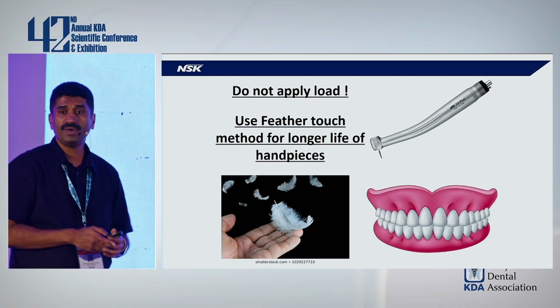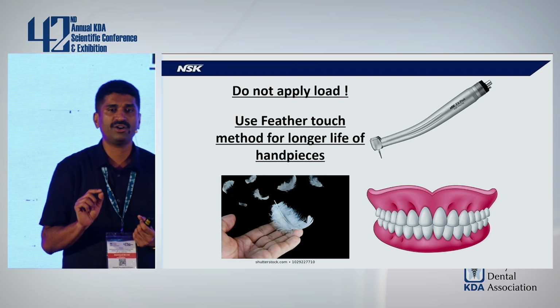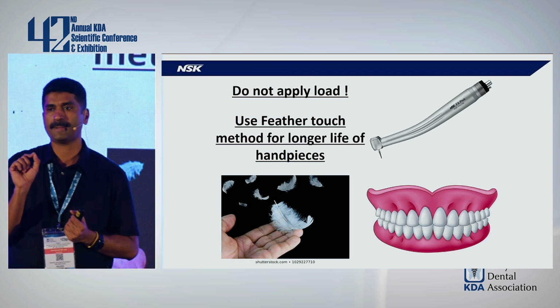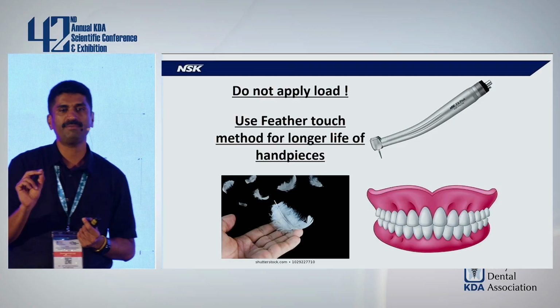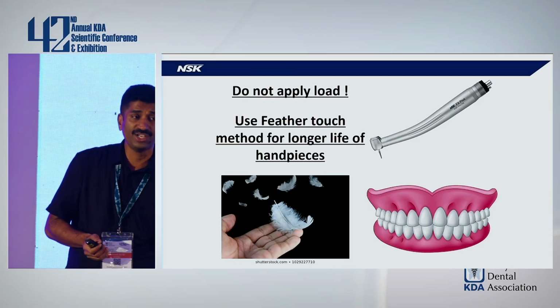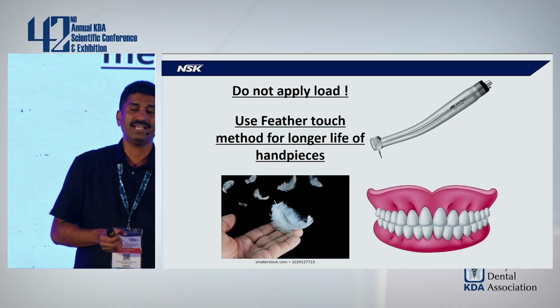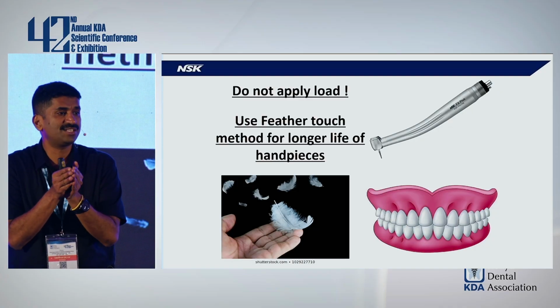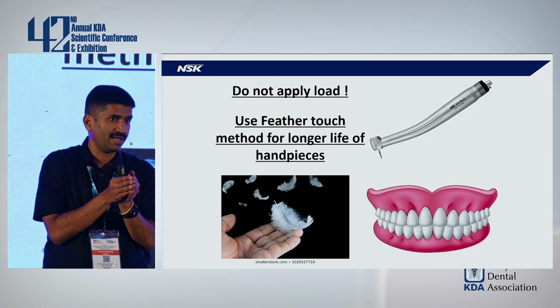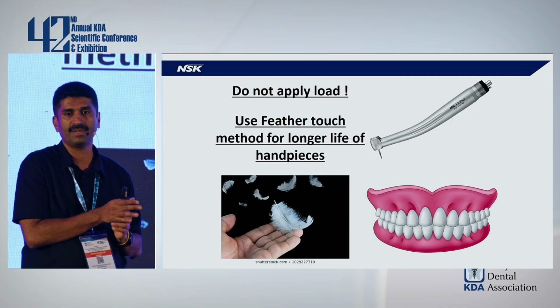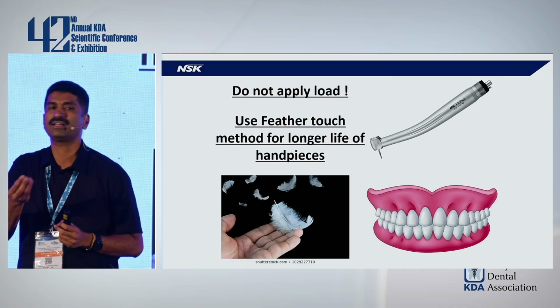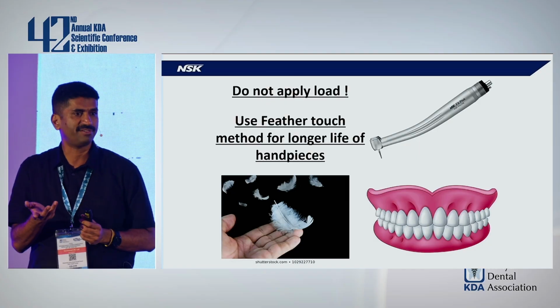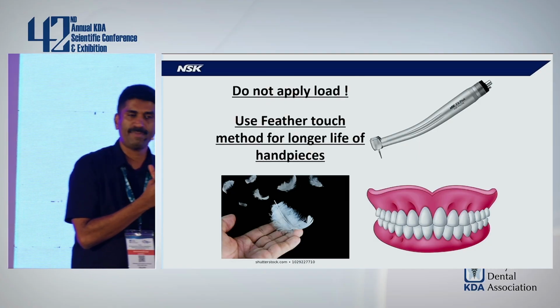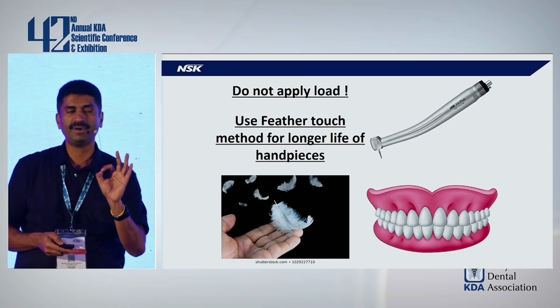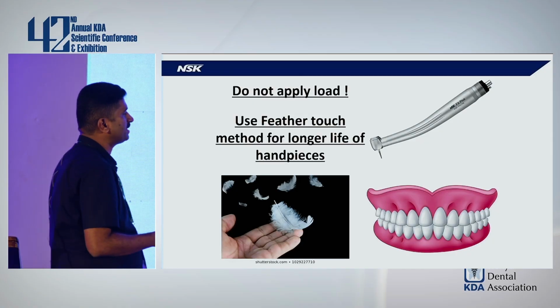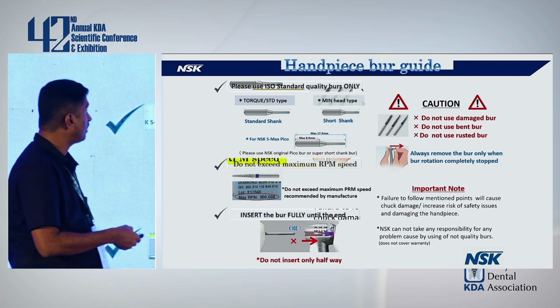So when I talk about burs, there is one more point you need to take care of. Please use good quality burs, okay? Always use good quality, ISO certified burs, and ensure that the burs you're using can withstand a speed of at least 350,000 RPM. As I said, our handpiece runs at 400,000 RPM. There are many burs in the market which are rated at 150, 200, 250. It will be written on the back side of the bur packet. Please ensure that you're using the proper criteria of burs. So that will take care of your handpieces.